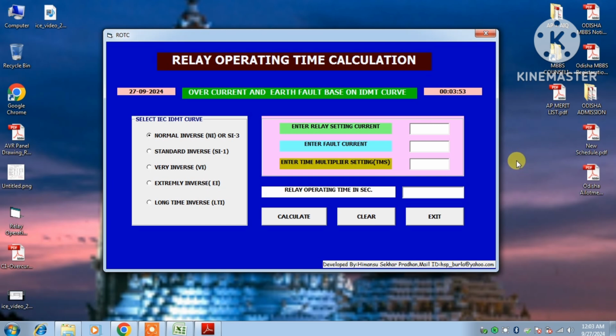So we have to select which curve we are generally taking. We can give the primary value or the secondary value. Suppose the CT ratio is 300/1 and the full load current we have taken is 300, then we can enter 300. Then enter the fault current, maybe 3 times or 4 times, so 4 times means 1200. And the TMS we can get from the relay setting file. Suppose 0.35 is the TMS. Suppose we take normal inverse or SI3, both are the same. Then if we calculate, automatically this is the relay operating time.